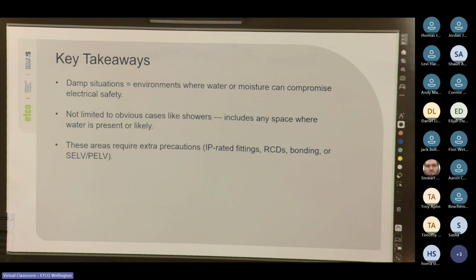Safety extra low voltage is like your 24 volt. So that would be like your garden lighting. PELV, I'm trying to remember the exact number. So protected extra low voltage. It's where the secondary winding of the transformer is earthed. So it's basically protected by a transformer.